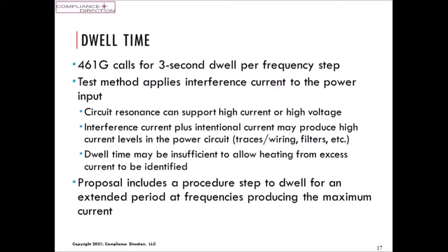Well, this test method I'm proposing does apply interference current to the source. So I'm seeing where I see a circuit resonance that can support a high current or a high voltage, meaning a high impedance or a low impedance, or a minima or a maxima on the curve. And the current plus the intentional current can produce these high current levels. So the dwell time, because it's a short duration event, may not be there long enough for us to see the damage that's occurring, an overcurrent event. Now, it could damage it instantly or pretty quick, but the heating effects may be just deteriorating the circuit.